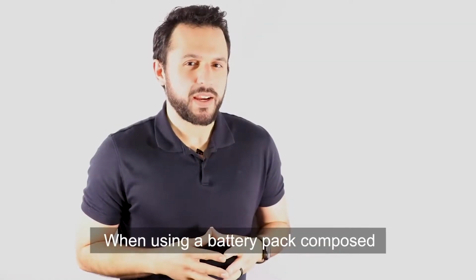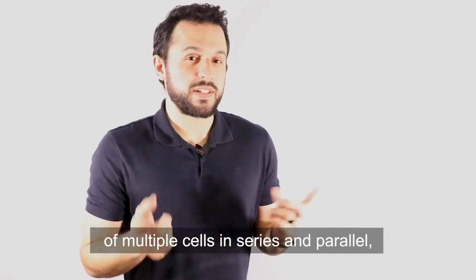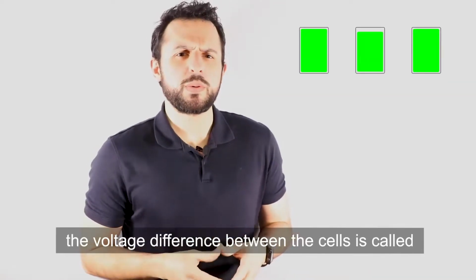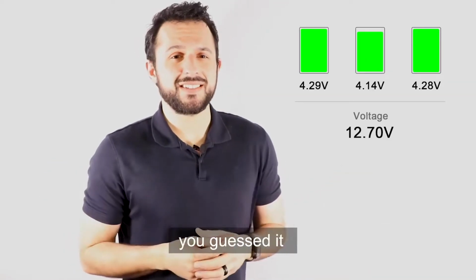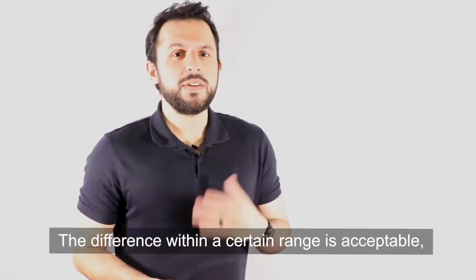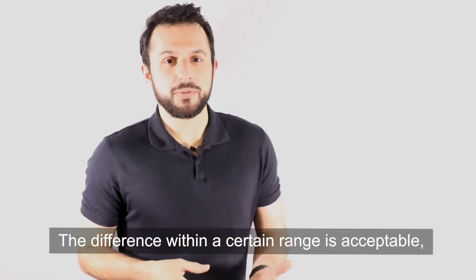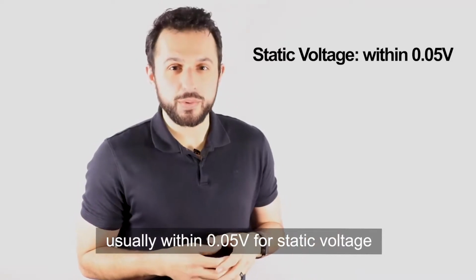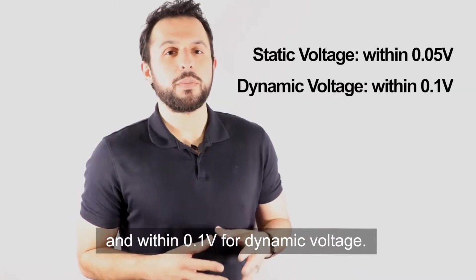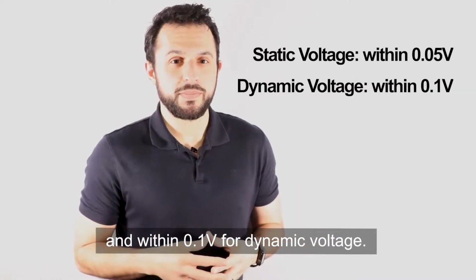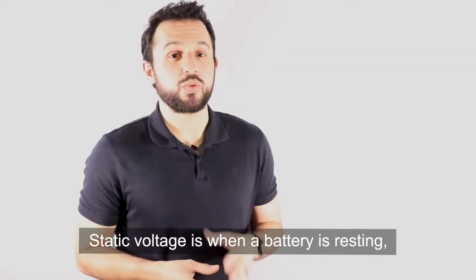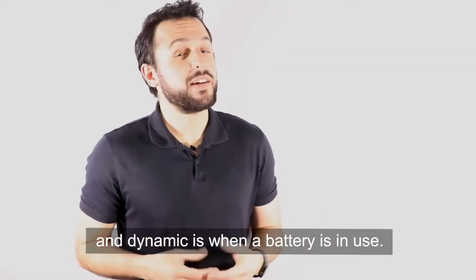When using a battery pack composed of multiple cells in series and parallel, the voltage difference between the cells is called, you guessed it, voltage difference. The difference within a certain range is acceptable, usually within 0.05 volts for static voltage and within 0.1 volts for dynamic voltage. Static voltage is when a battery is resting, and dynamic is when a battery is in use.